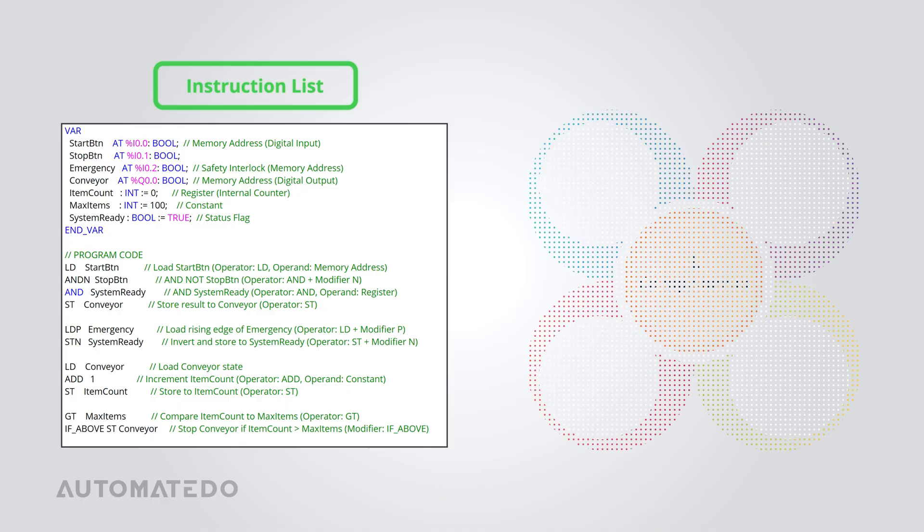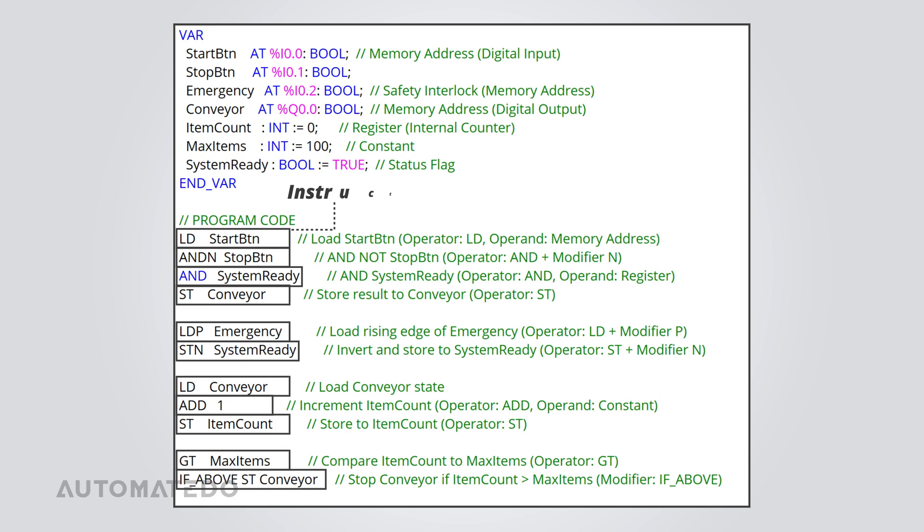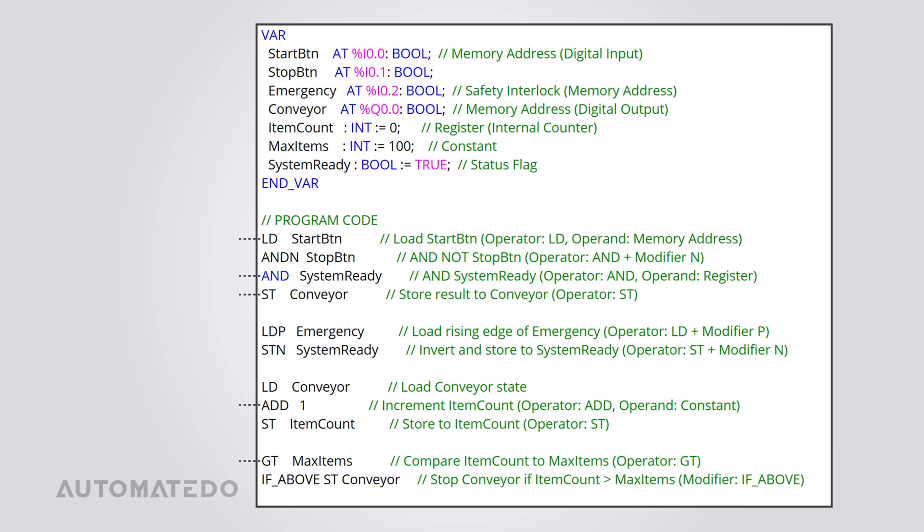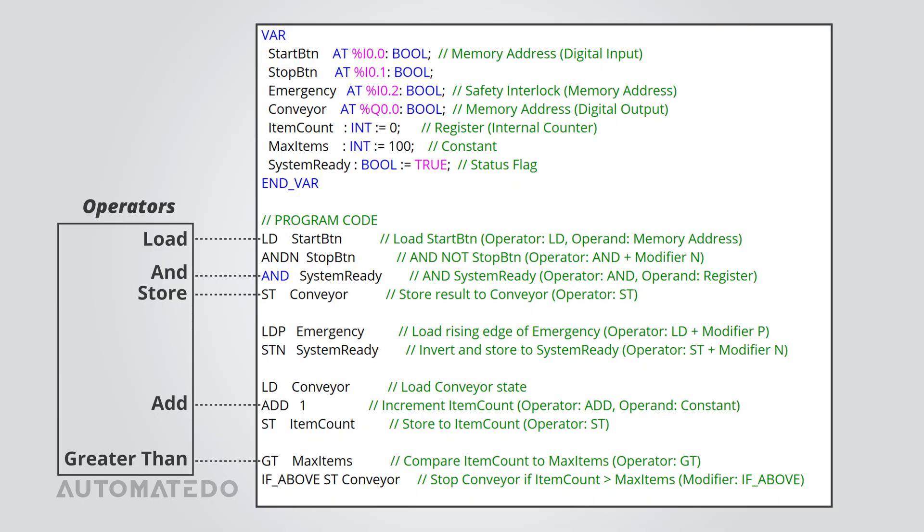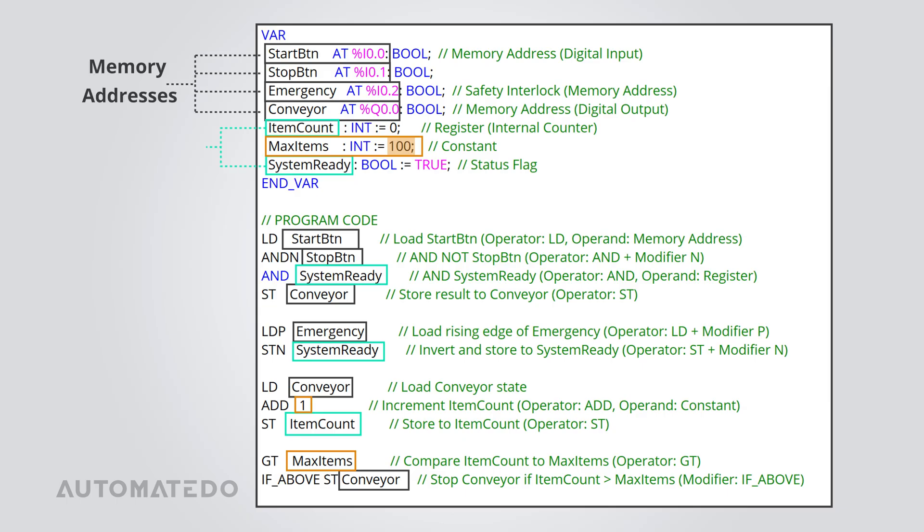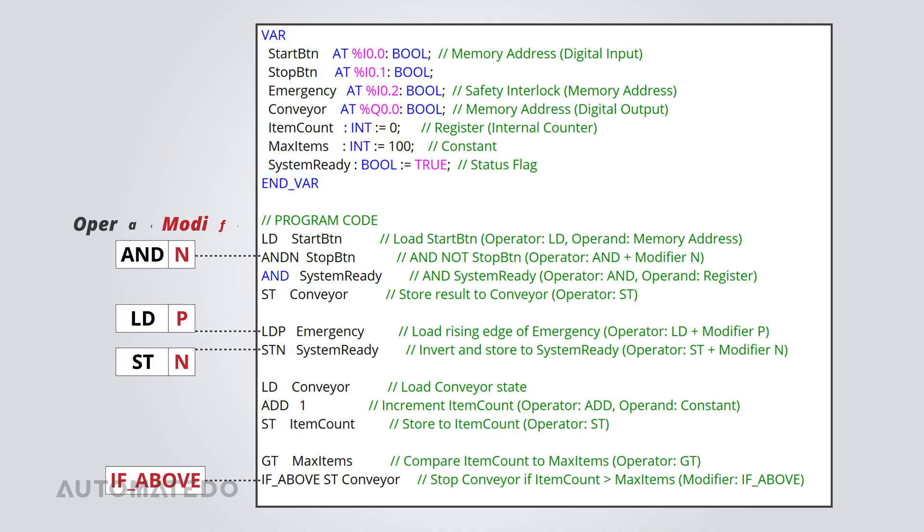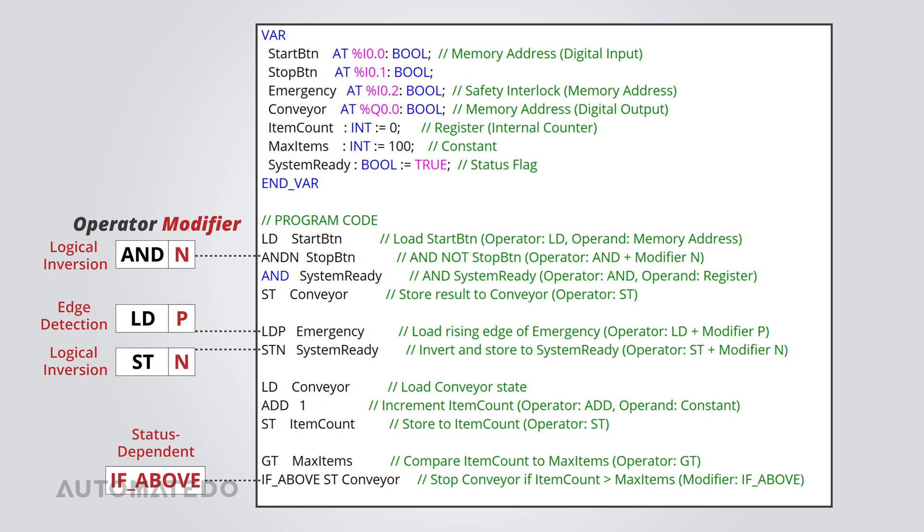In an IL program, everything boils down to four key components. Each line of an instruction list represents exactly one instruction. Then there are operators, which are the actual commands that tell the PLC what to do, always written in standardized mnemonics. Operands come next. They're the elements that operators act on, whether that's memory addresses, registers, or constants. Lastly, we have modifiers to tweak the default behavior of operators, allowing for logical inversions, edge-sensitive execution, or even status-dependent operations.